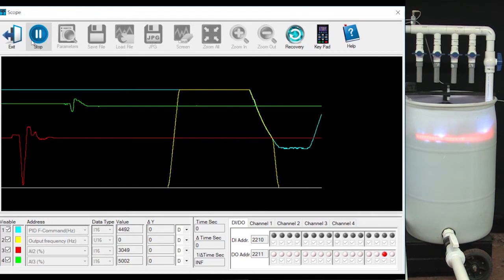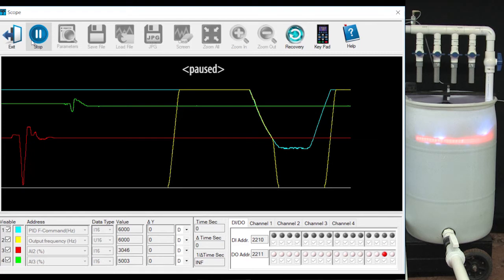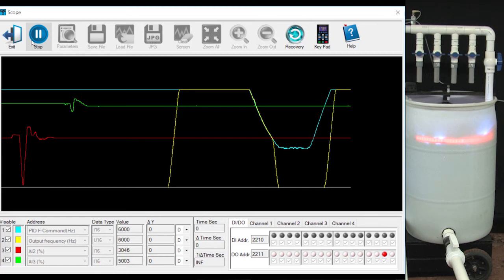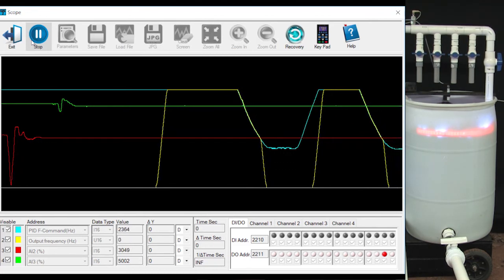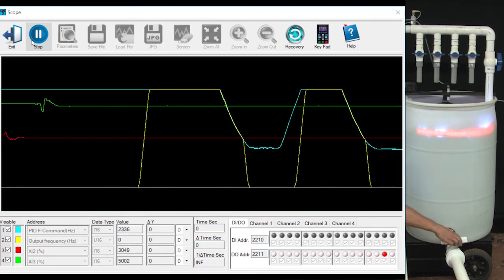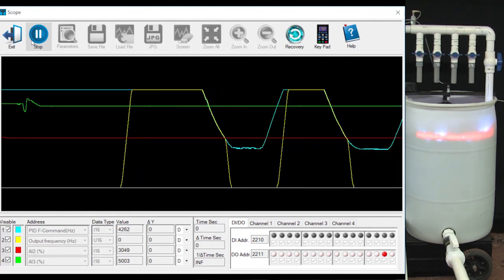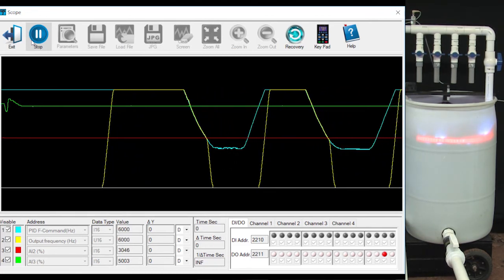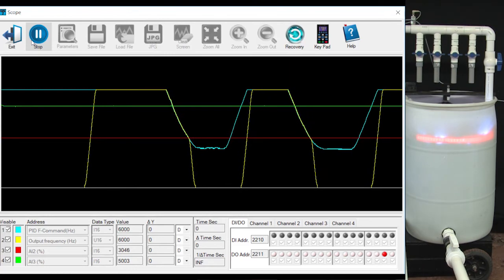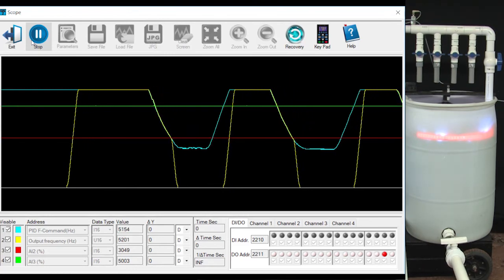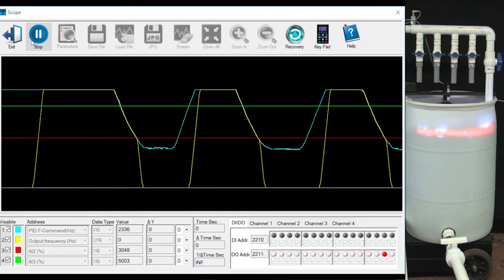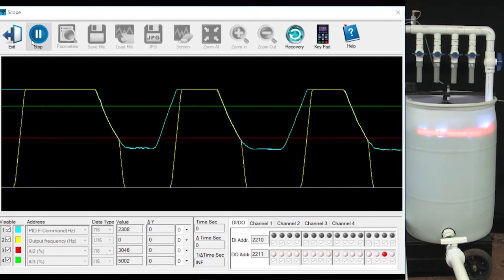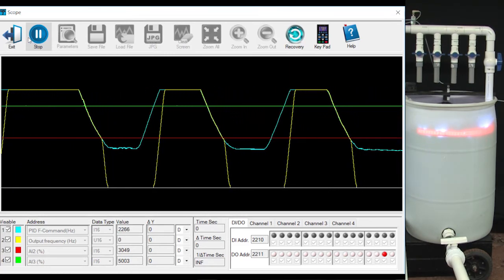If I open the valve to create some demand, the blue PID frequency command goes up to try and compensate and when it crosses the green 50 Hz wake up level, sleep mode allows that to pass through to the output frequency which goes to the motor. Again, exactly what we expect. So now the GS4 drive is automatically filling the tank as needed by watching that PID generator frequency command and is only letting that through to the pump when it is efficient to do so.